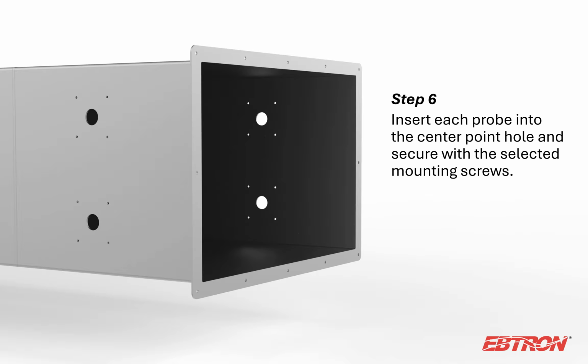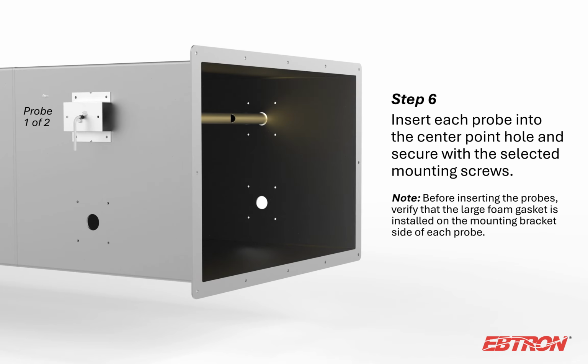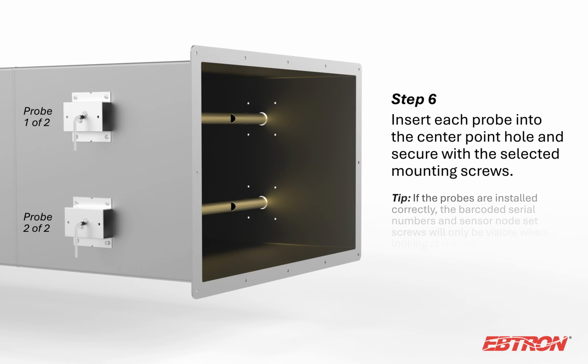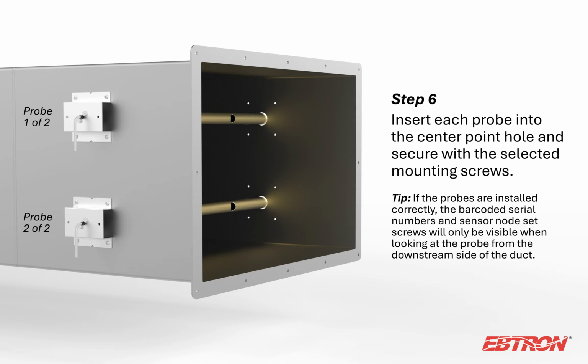Start by inserting the first probe on the insertion side into the center point hole. The airflow directional arrow should point in the direction of airflow. It is okay if the arrow is upside down. Secure the insertion mounting bracket with the 4 selected mounting screws. Repeat this for each additional probe location.